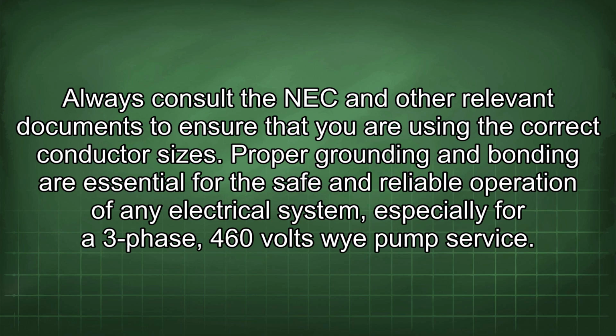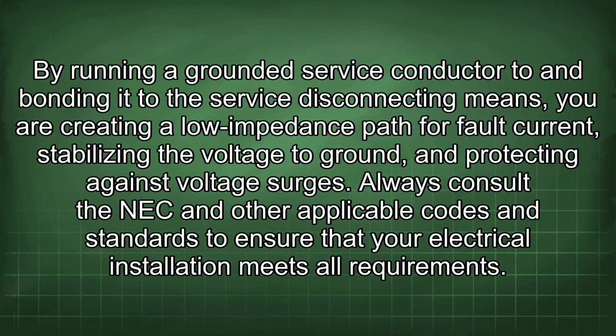Proper grounding and bonding are essential for the safe and reliable operation of any electrical system, especially for a 3-phase, 460 volts Y pump service. By running a grounded service conductor and bonding it to the service disconnecting means, you are creating a low impedance path for fault current, stabilizing the voltage to ground, and protecting against voltage surges. Always consult the NEC and other applicable codes and standards to ensure that your electrical installation meets all requirements.